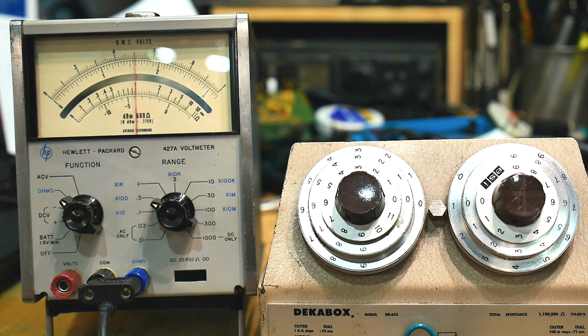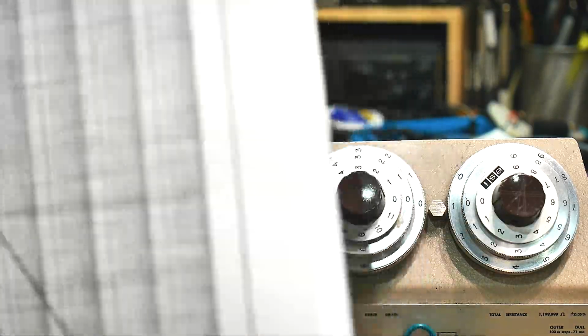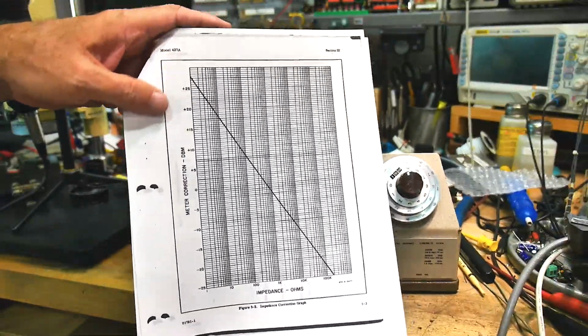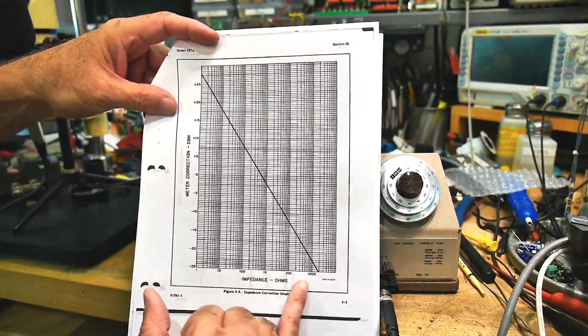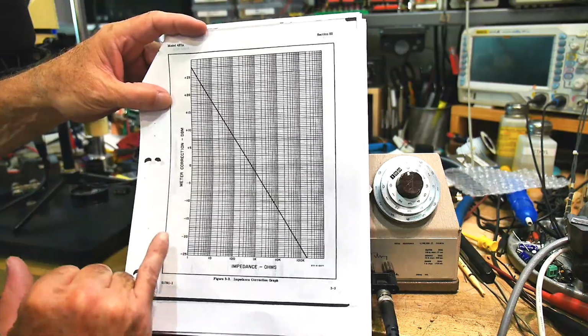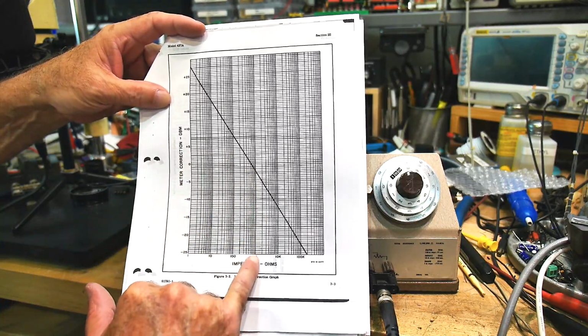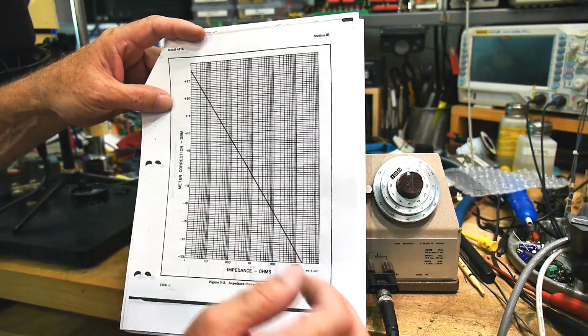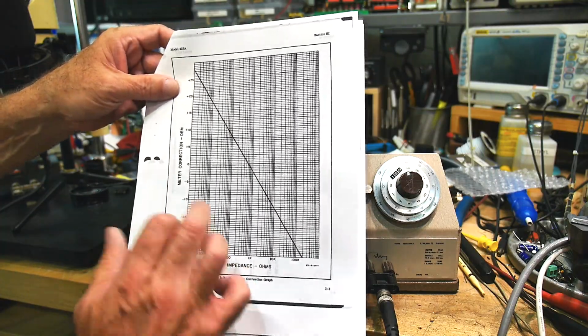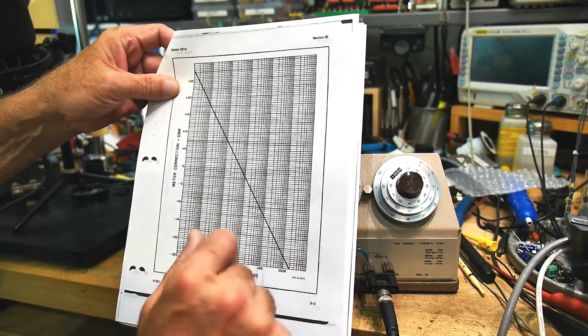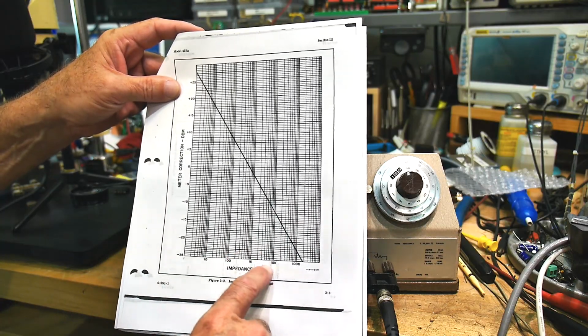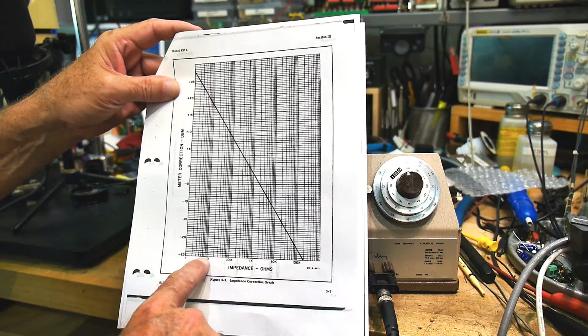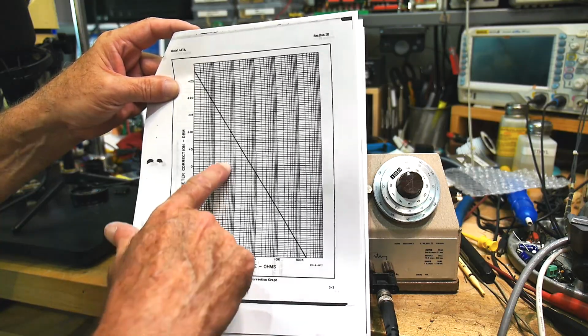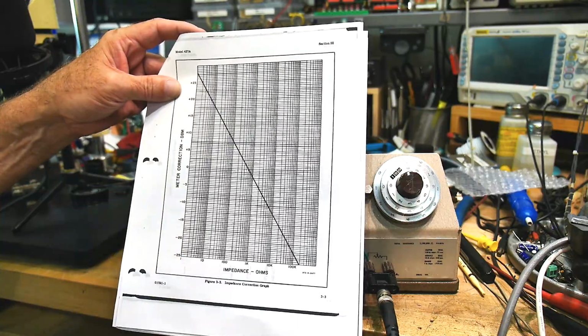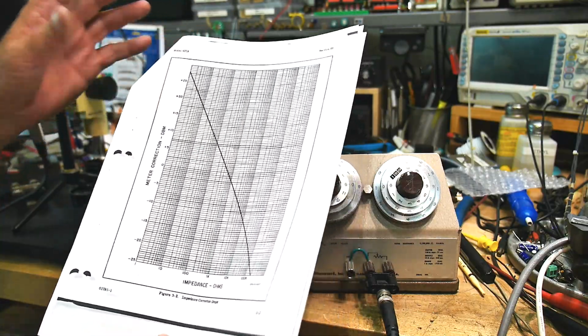See if I can find that quickly. Here it is. If you can see that. This gives you whichever impedance you have and the meter correction. So 0 comes down to 600. Okay, so the zero will be at 600. And so let's say you're operating at 50 ohms, then this is 10, 20, 30, 40, 50 ohms. So the correction is like plus 10. So you can use this.